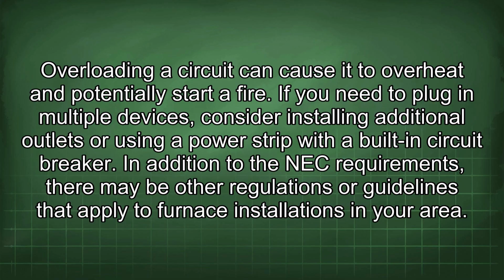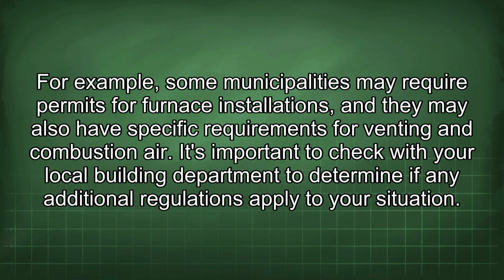In addition to the NEC requirements, there may be other regulations or guidelines that apply to furnace installations in your area. For example, some municipalities may require permits for furnace installations, and they may also have specific requirements for venting and combustion air. It's important to check with your local building department to determine if any additional regulations apply to your situation.